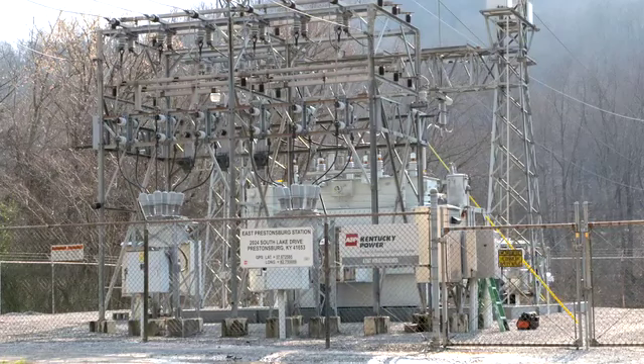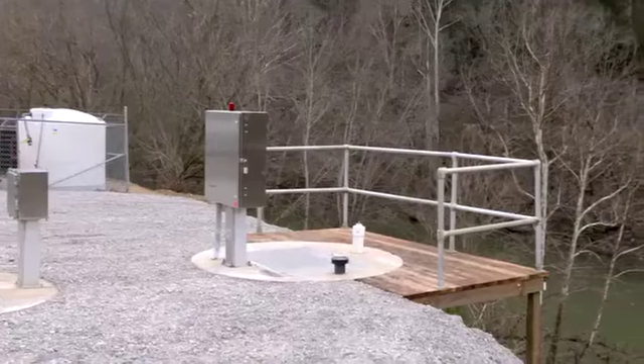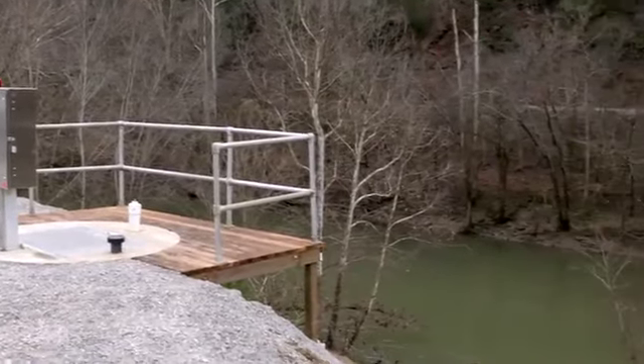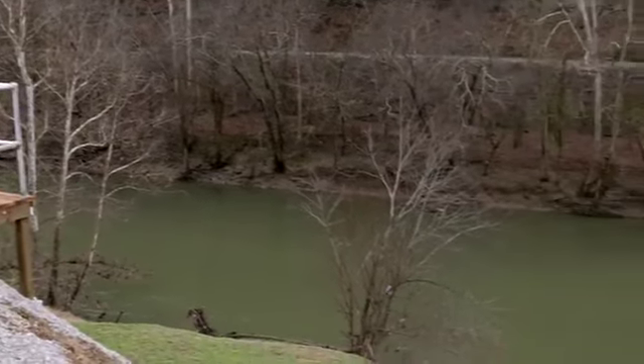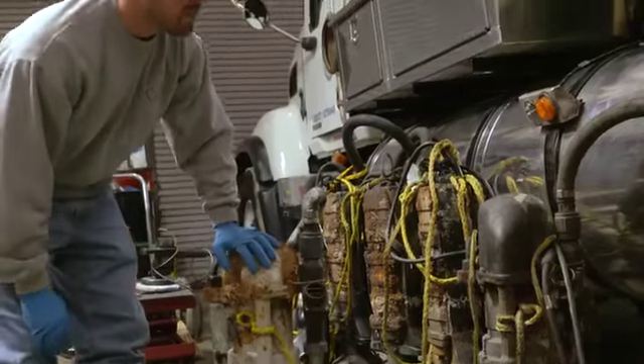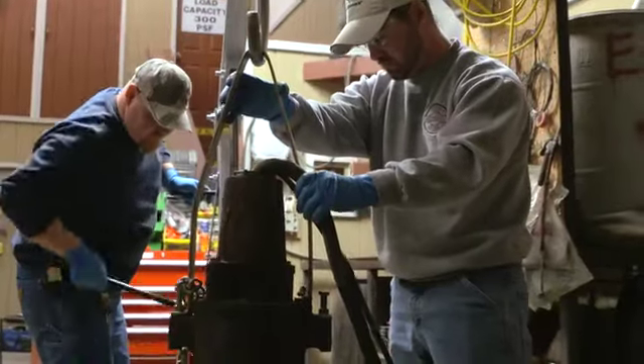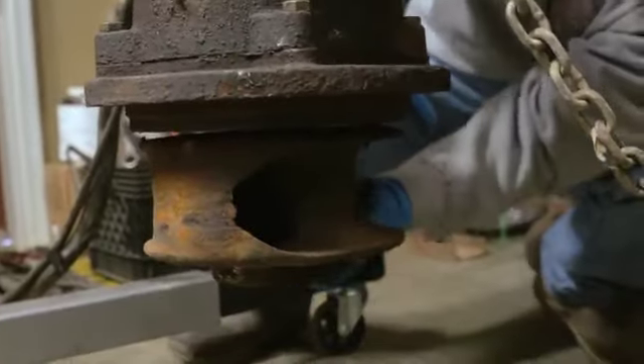The station's pumps were also shutting down unexpectedly due to an unreliable electric feed from the local utility. To prevent sewage overflow into the adjacent river, the pumps cycled on and off very frequently — every ten to fifteen minutes on average — putting mechanical stress on the system. We have seal failures; we eventually got to winding breakdowns on our pumps and a lot of wear on our impellers.